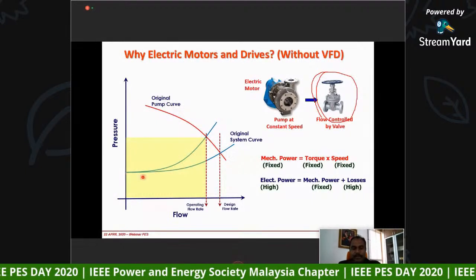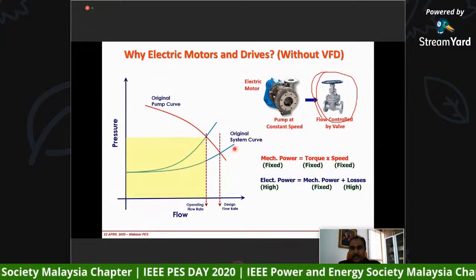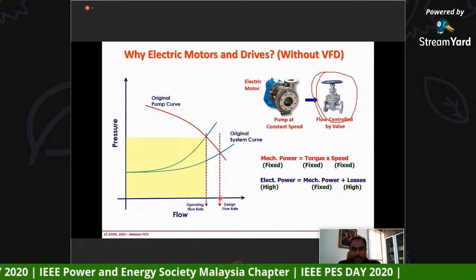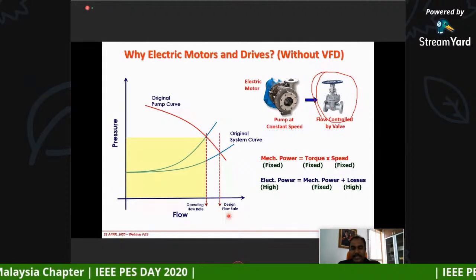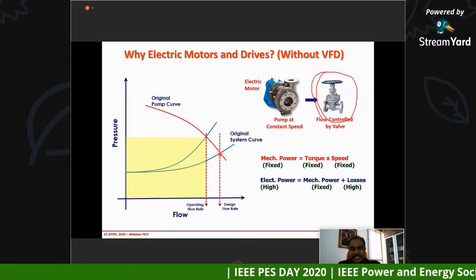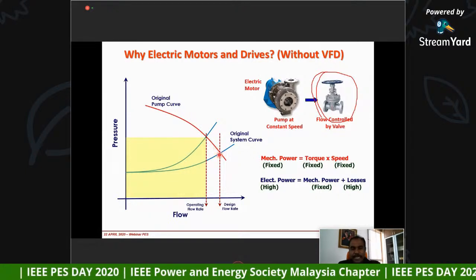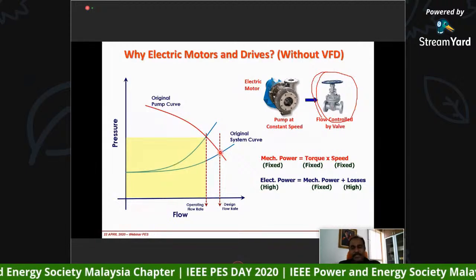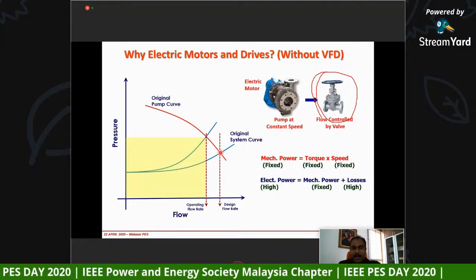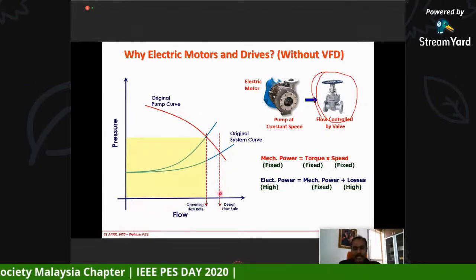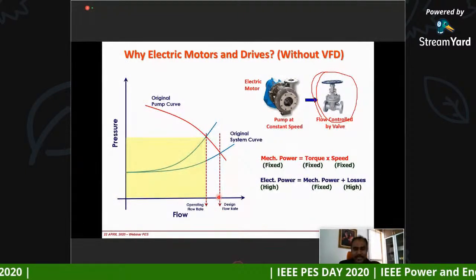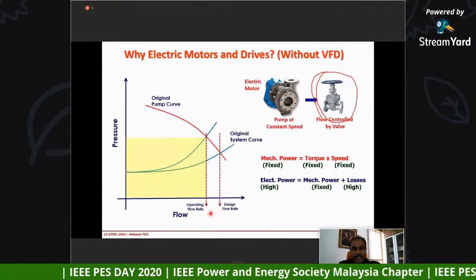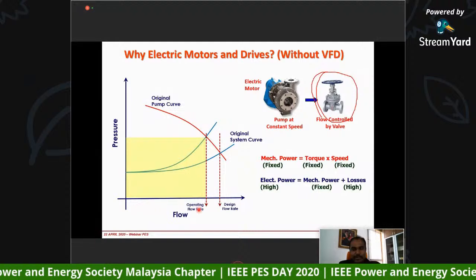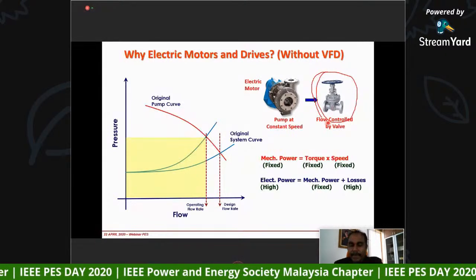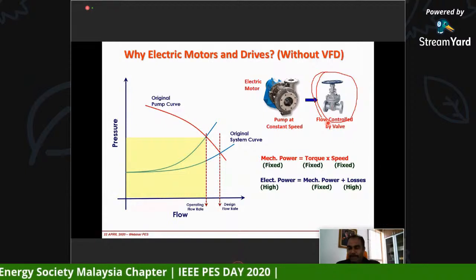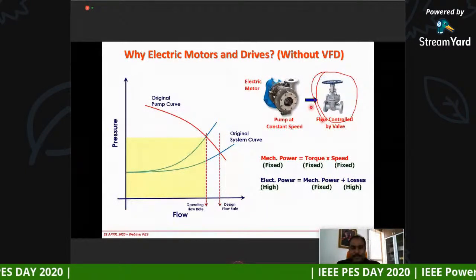Normally, when we design, we will have a system curve, the original system curve. We'll be designing it for one particular design flow rate. Let's say we are designing at this particular point. Once we have decided, we install the pump and start to operate it. But when you operate the pump, usually we don't run at this particular flow. Usually we'll be running at a reduced flow rate, and let's say over here is an operating flow rate. How do you reduce the flow rate? By controlling the mechanical valve. So you control the mechanical valve to reduce the flow rate, and then your operating point is going to be here.